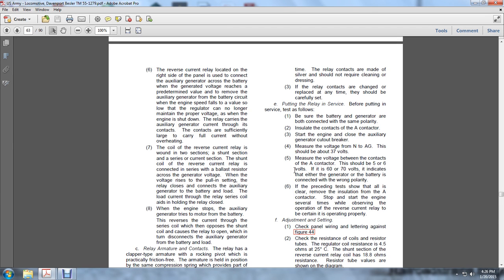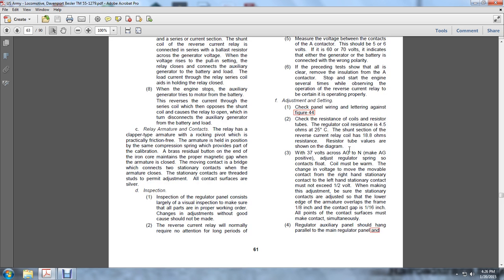If the preceding test shows all clear, remove the insulation from the A contactor. Stop and start the engine several times, observing the operation of the reverse current relay to see that it operates properly. Adjusting: see the panel wiring and lettering, figure 44. Check the resistance of the coils and resistor. The regulator coil resistance is 4.5 ohms at 25 degrees Celsius. The shunt section of the reverse current relay coil has 18.8 ohms resistance. The resistor values are shown in the diagram.